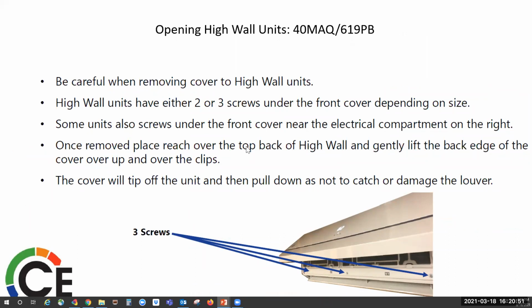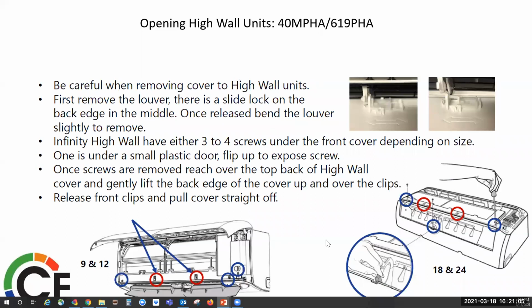Before removing the covers on these, you want to remove the screws. Sometimes the screws are hidden. Just be careful when you are removing them. On these high walls, sometimes you have to kick up the louvers and remove the screws. These are usually located in the back of the service manual for both the indoor and outdoor unit. It tells you where things are located at: sensors, screws, things like that, how to remove the blower or how to even remove the condenser fan motor.